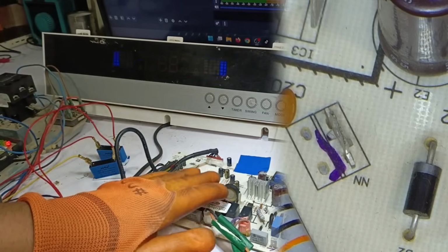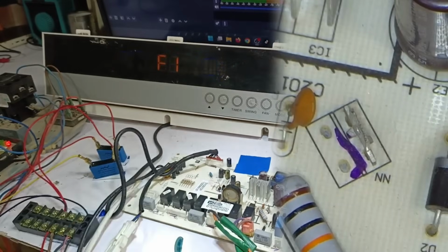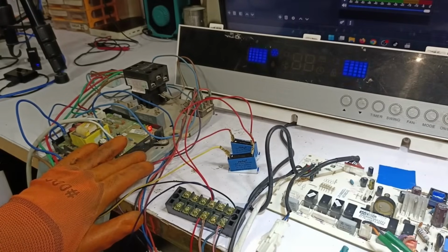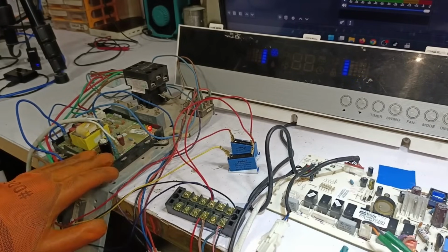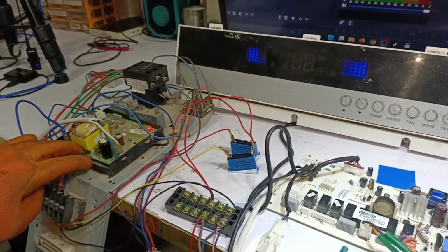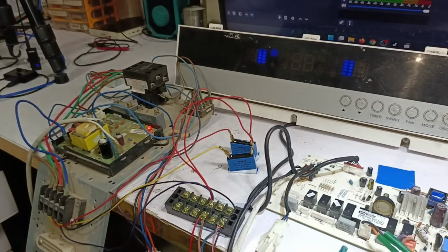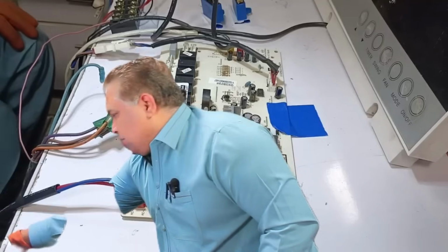This confirms that our indoor unit and its signal circuit are completely fine. The only issue is with the signal itself. There is no other problem at the indoor side. Now, our full focus will shift to the outdoor circuit because the fault lies there. We will continue checking to find out what exact issue in the outdoor unit is causing this problem. For now, we will turn off the system. Now, we will test the outdoor PCB to find out what problem is causing this issue.